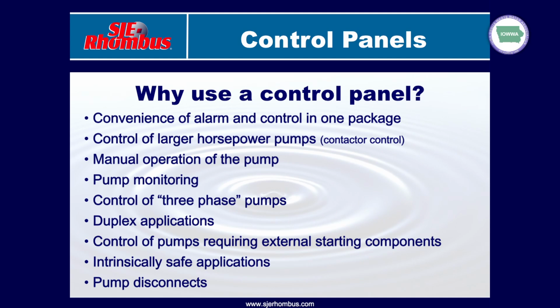Pump monitoring, we can add things like elapsed time meters or cycle counters to a control panel that lets you know exactly what kind of usage we've seen on our system. If we've got a three-phase pump that we're trying to operate, there's not a float switch made that'll operate a three-phase pump. So anytime we've got three-phase pumps, which generally is going to be a commercial application, it's going to require the use of a control panel.